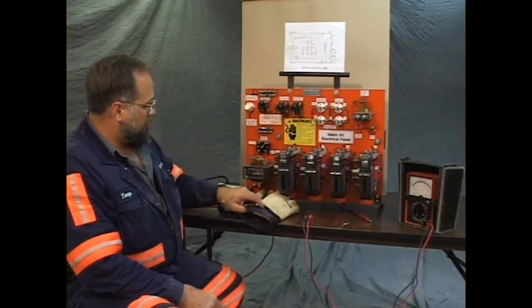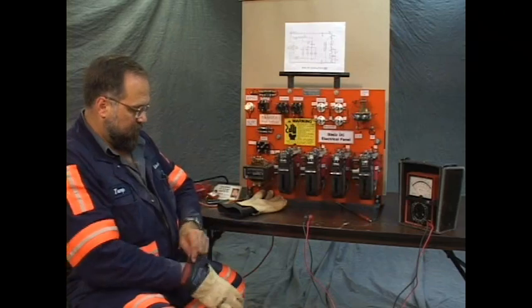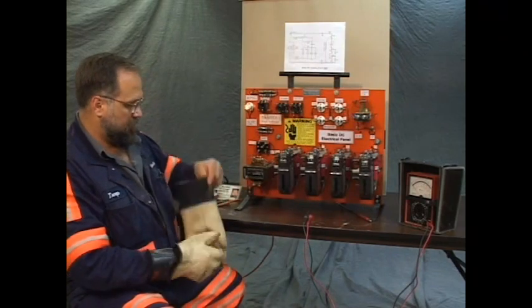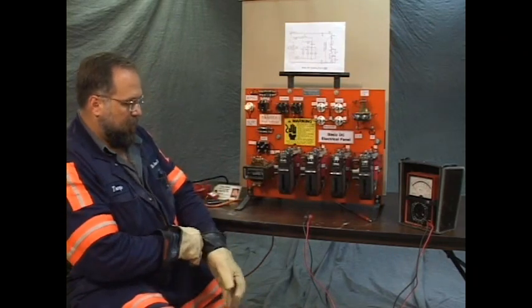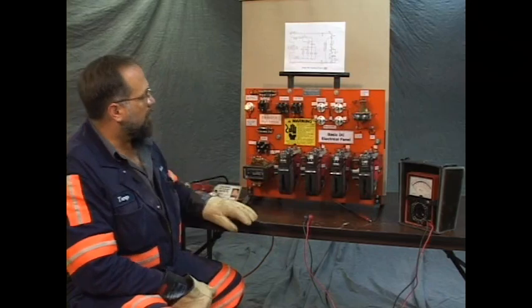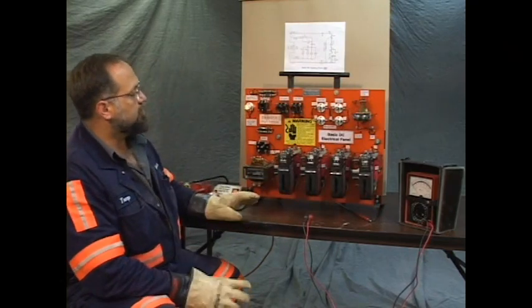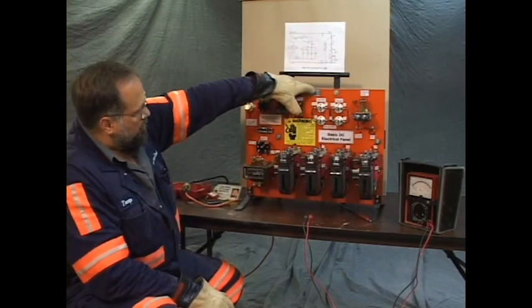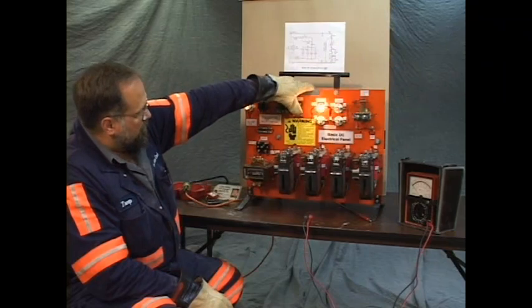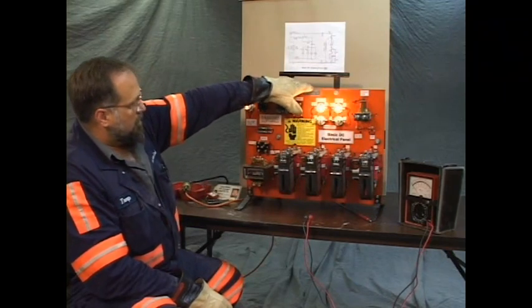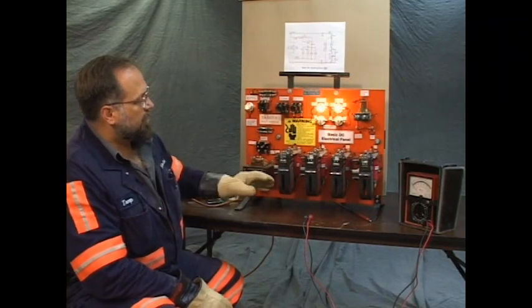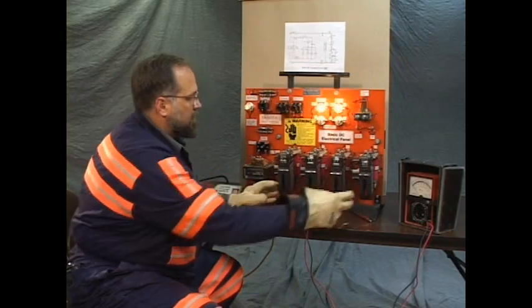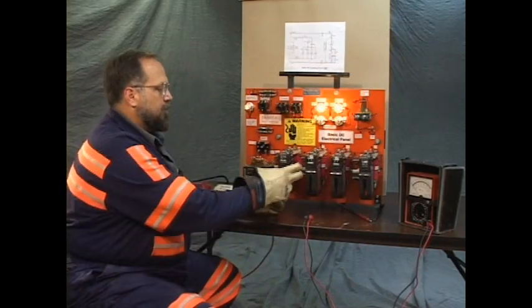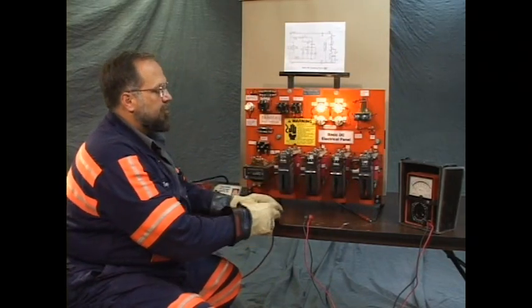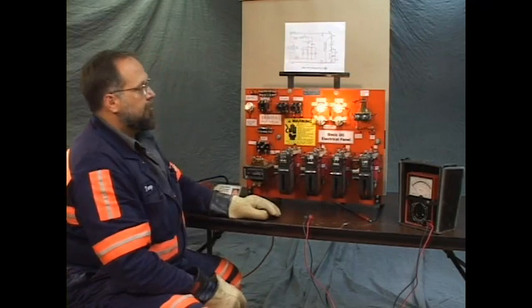Well, let's glove up. And we're going to operate the panel for normal operation, show you what it should be doing. You heard the 3 clicks. M1 and M2 close simultaneously. And after an interval, 1A closes. Then after another interval, 2A closes.